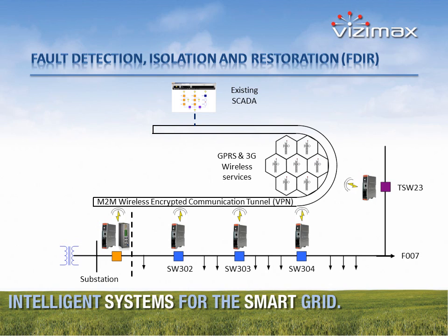One of the main applications of the RightWON product is fault detection, isolation, and restoration, commonly called FDIR. The objective is to detect faults on the distribution system, isolate them automatically, and report these faults to a central SCADA system for public utilities, aiming for the shortest possible power interruption by automating distribution equipment in the field.